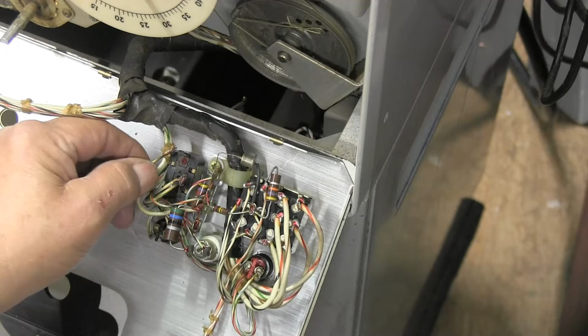I'll grab a voltmeter. I want to check across that switch. In the off position, I'm not reading nothing. Let's go to the on position. And in the on position, it doesn't read any continuity, but yet the amplifier will not shut off.